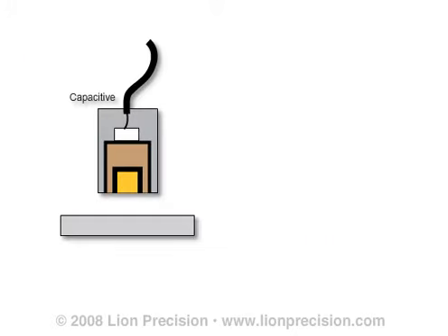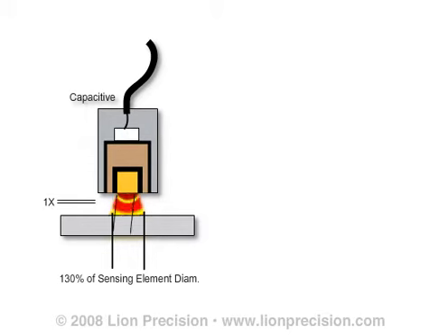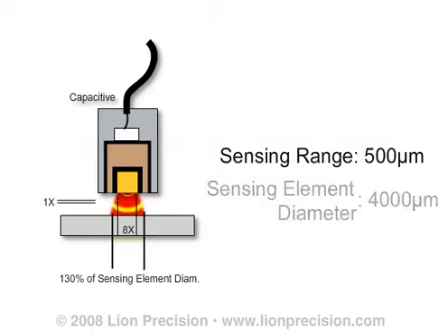Capacitive sensors use an electric field for sensing. This field is focused by a guard ring on the probe, resulting in a spot size about 30% larger than the sensing element diameter. A typical ratio of sensing range to the sensing element diameter is 1:8. This means that for every unit of range, the sensing element diameter must be 8 times larger. For example, a sensing range of 500 microns requires a sensing element diameter of 4,000 microns, or 4 millimeters. This is for typical calibrations. High resolution and extended range calibrations will alter this ratio.